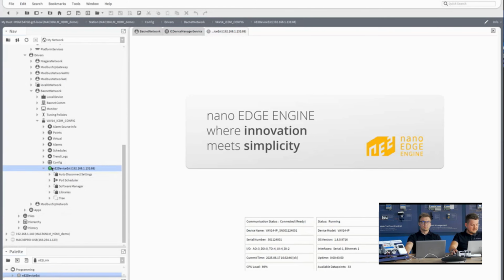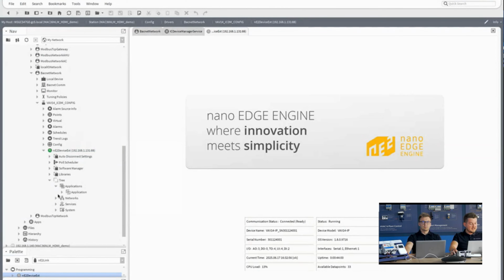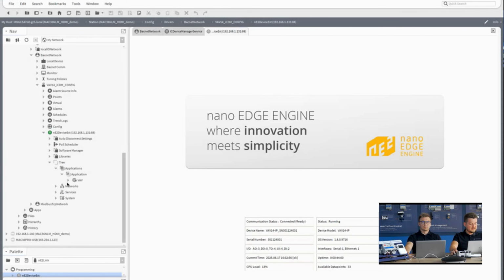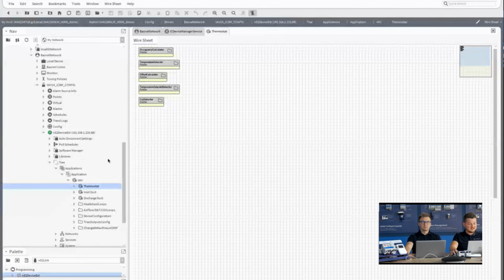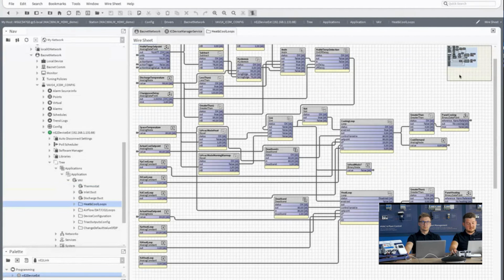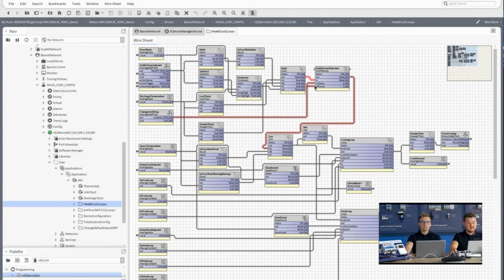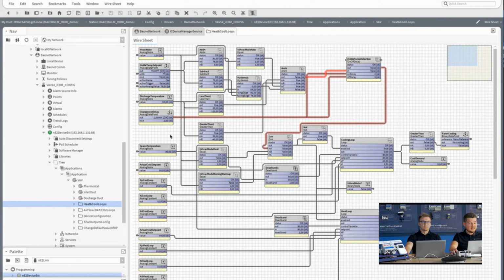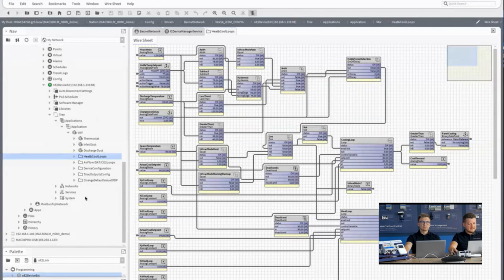So in the meantime, as you can see, we have the green LED right here. We can see that the device is the VAV 14IP. I can expand this tree, and I can go directly to the application itself. There's a container called VAV, and we can see here we have different folders and sub-equipments like the thermostat. And yeah, I can access the whole VAV application directly in my Niagara instance. I can change it, or you can add a new application and utilize the leftover IOs and write a control logic in addition to the default one here using Niagara Workbench. And all of this can be done using the USB port.